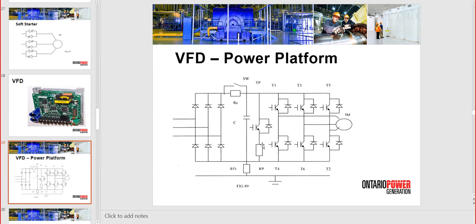So this leg is the dynamic braking in the DC bus, and the next is the actual bridge of 6 IGBTs with reverse diodes, and those are the actual inverter. So the inverter, as you see, depends on which direction we fire those IGBTs. We create a magnetic field in one direction, or in reverse if you change the order of the pulses. It is always 2 conducting, one on one side and one on the other. And if we want, we can also perform quick plugging by reversing the field in the induction motor. Also, what we can do is DC injection braking by turning on certain IGBTs permanently, like 2 on the top and 1 on the bottom on the other leg, and then you freeze the magnetic field in the induction motor. And if the magnetic field in the stator is frozen, then the cage will follow and will stop.